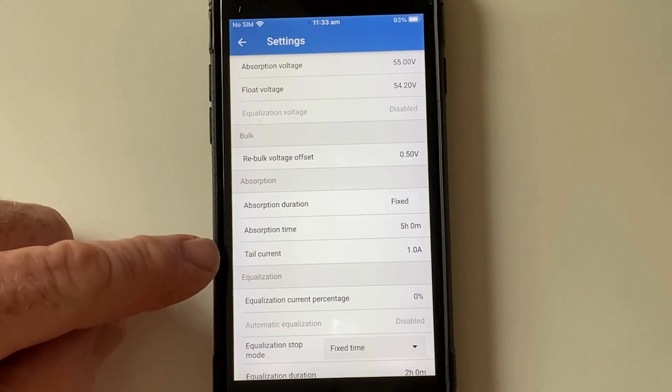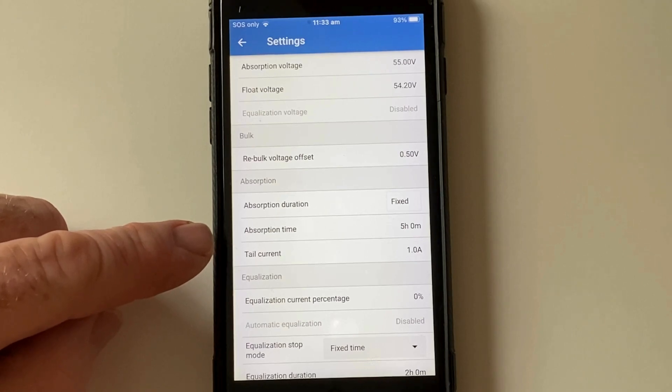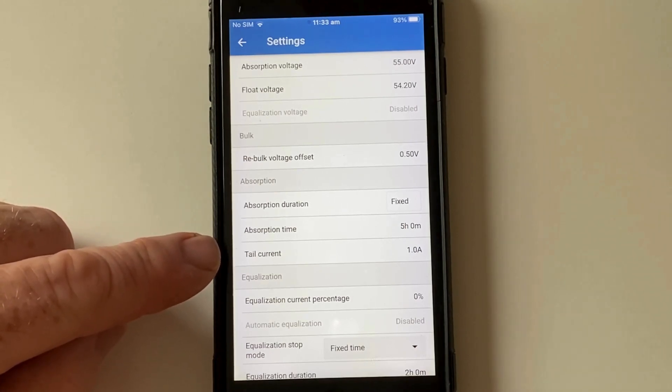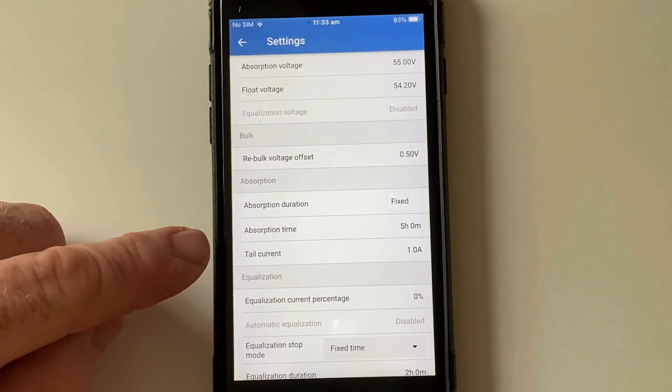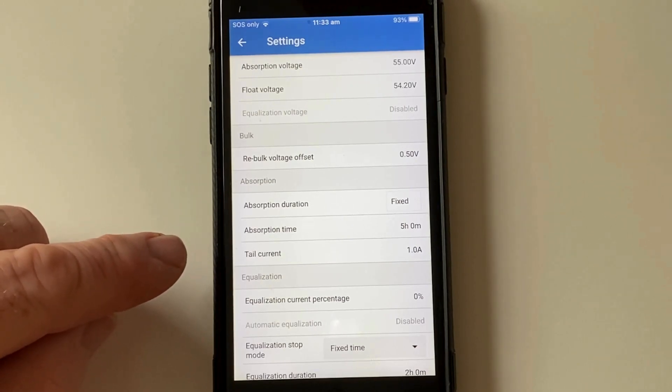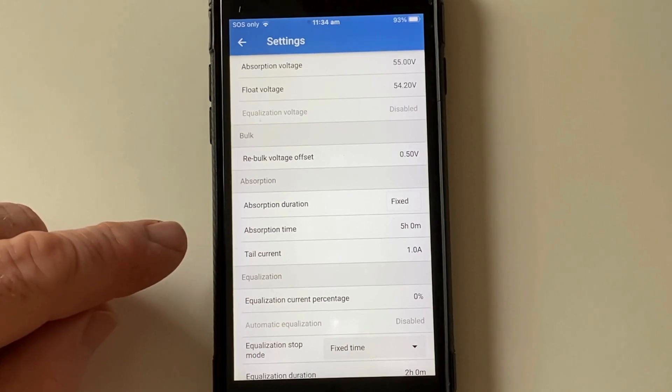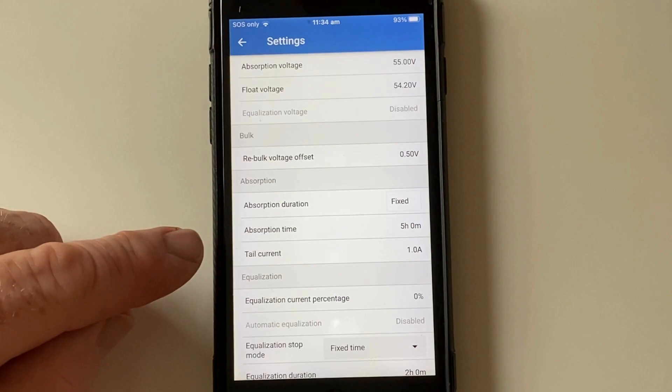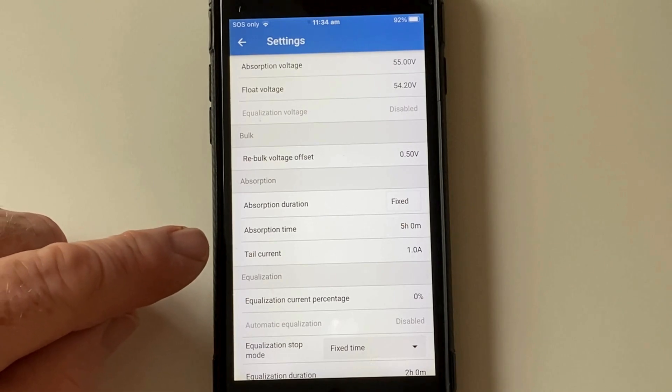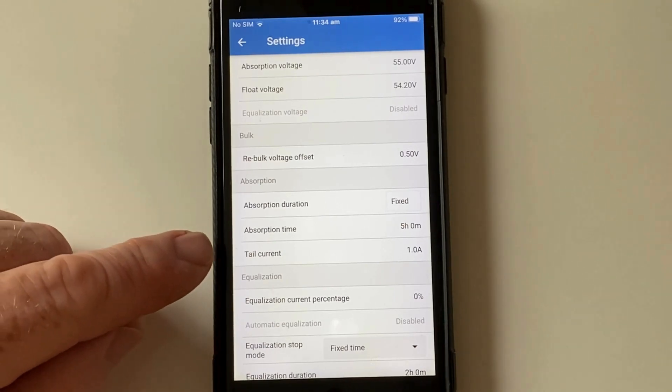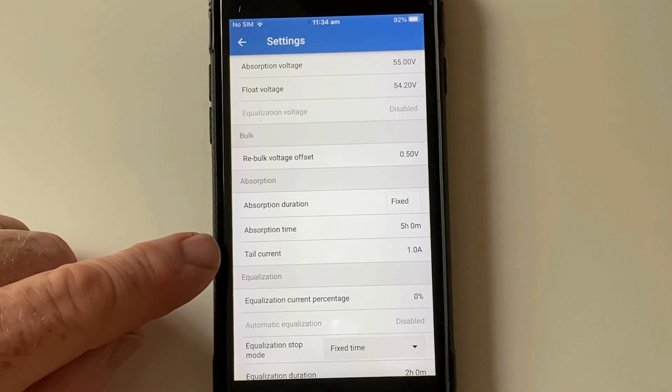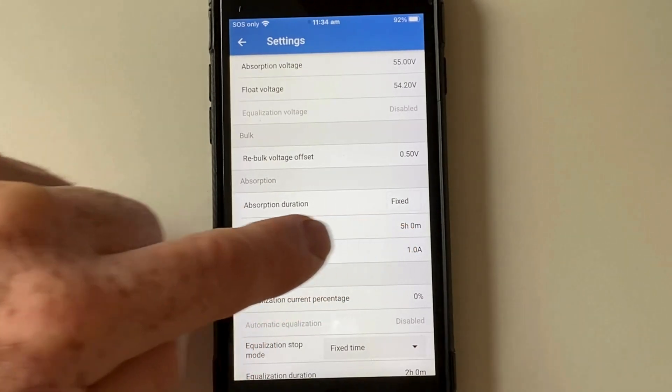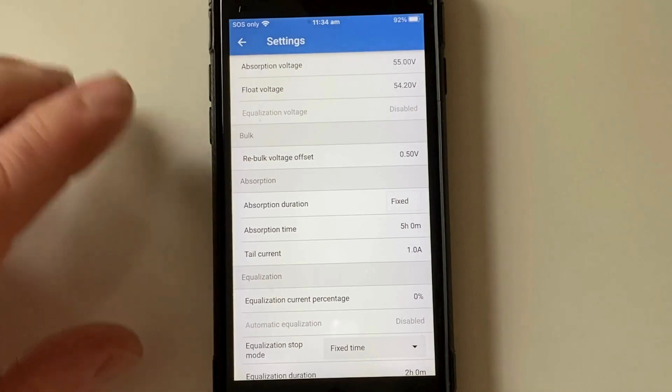The tail current here is when the system considers the battery to be fully charged. So once the charger is charging at less than one amp, it will stop charging. And the battery monitor will detect that charge voltage. And after a certain amount of time, once that tail current threshold has been met, it'll set the state of charge to 100%. So that just happens automatically. You don't have to worry about that. The tail current is just telling you that once the charge current has dropped below that point that you've set, the system knows the battery is full and it will just go into float.